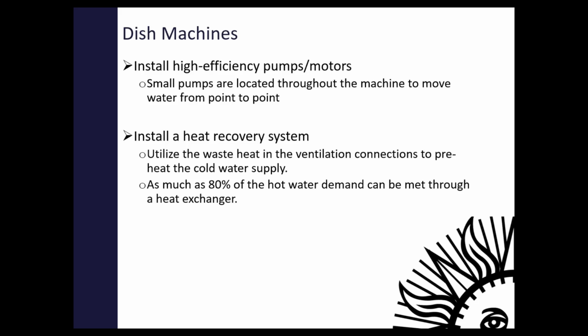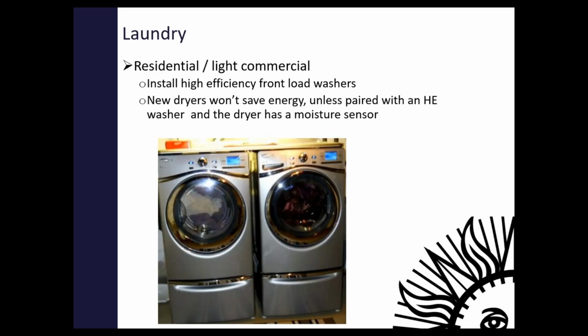Almost every dishwasher has a booster heater to heat the water from usually 140 coming into your commercial kitchen up to 180 to provide that final rinse for your dishwasher. So using a heat reclaimer to preheat, go from air to water, preheat that incoming water can save you some energy. In some cases, a lot of energy, but I think I've estimated mine more at 50% rather than 80. Moving into laundry, residential and light commercial, you won't really find much to do.